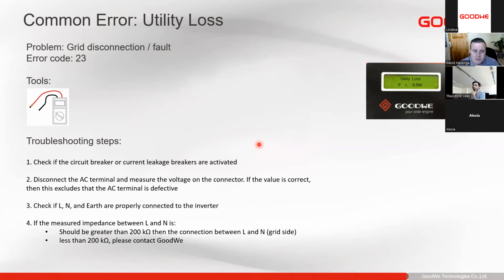We can check live, neutral, and earth are properly connected under the inverter as well, and also measure the impedance between live and neutral on the inverter. Once you've disconnected the ground, it should be greater than 200 kilo ohms, then the connection between live and neutral on the grid side is correct. If it's less than 200 kilo ohms, then please contact support for us to assist you.